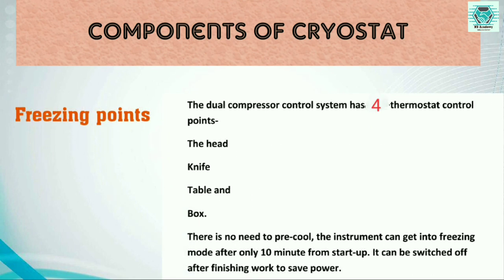There are four freezing points. The dual compressor control system has four thermostat control points: the head, the knife, the table, and the box.